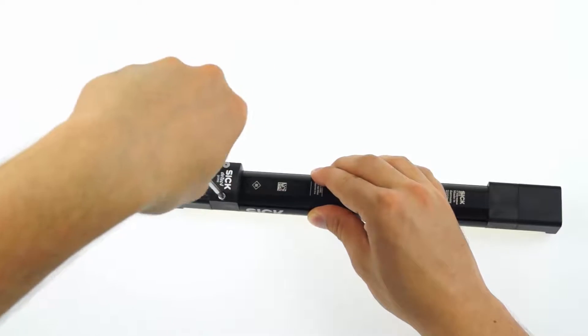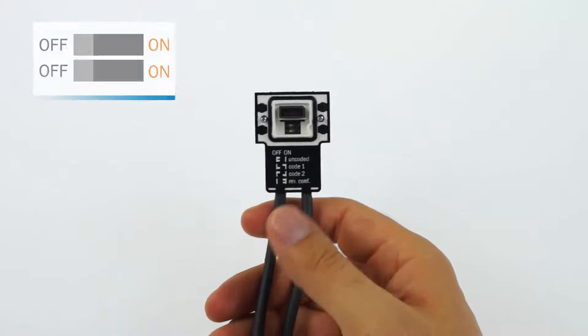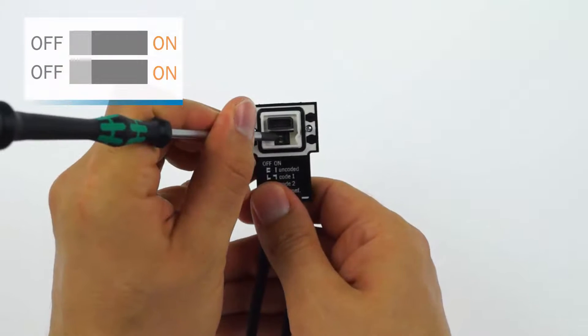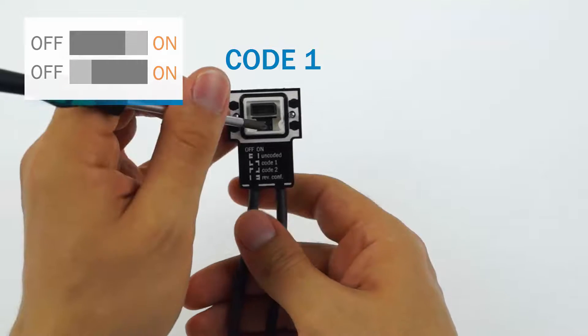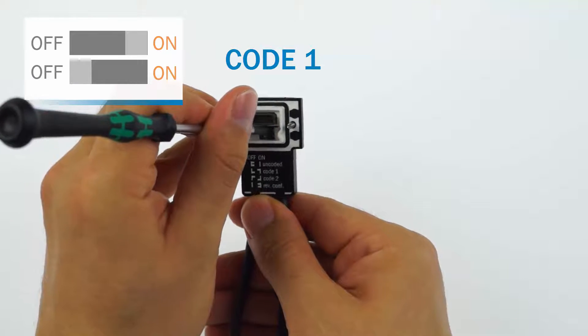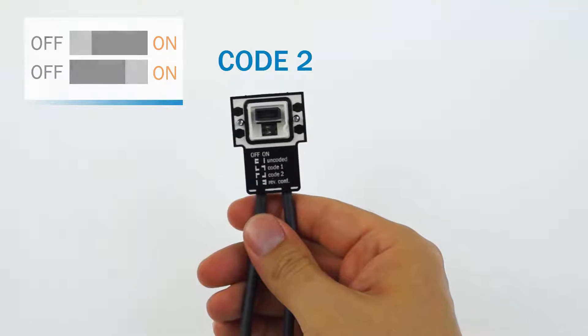Then detach the system plug by loosening the two retaining screws. On the system plug you find two DIP switches. With those switches you can set two different codes by either setting the first switch to ON and the second switch to OFF or vice versa. Make sure to code all corresponding devices accordingly.